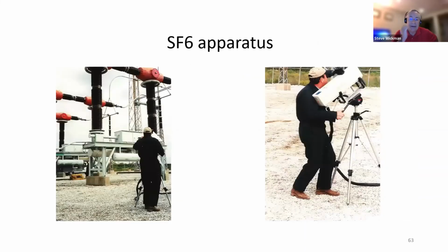Jumping to SF6 apparatus, kind of briefly here. This picture tells a couple of stories. It's an older Westinghouse SF6 breaker, and it's an older photo. The gentleman using the leak detection camera there, an older style camera, is not wearing the typical PPE that you'd see in a substation today. So this was from quite a while ago. And it says, as long as these breakers have been in service, they've been leaking. As long as they've been leaking, we've been addressing those leaks for the customers with such apparatus.